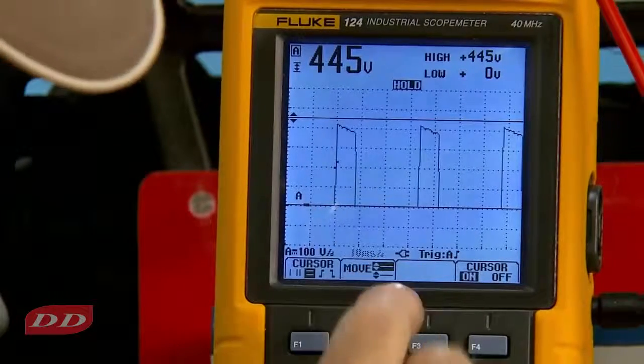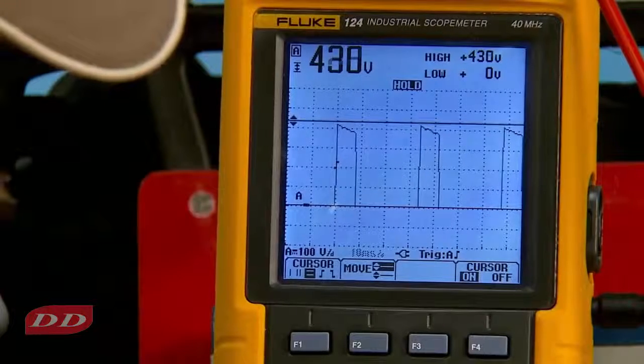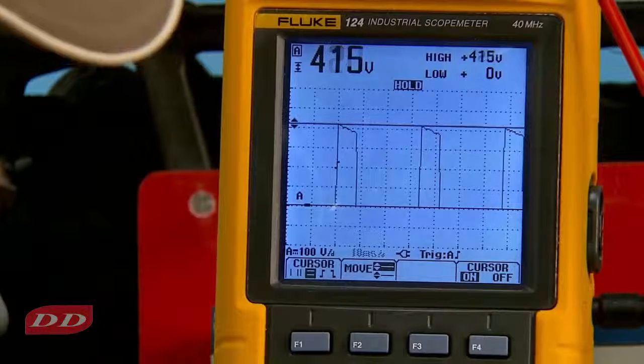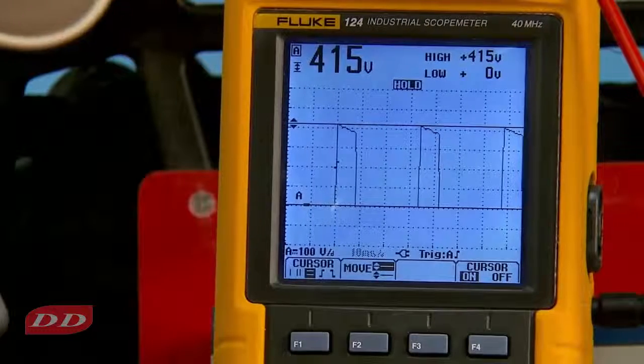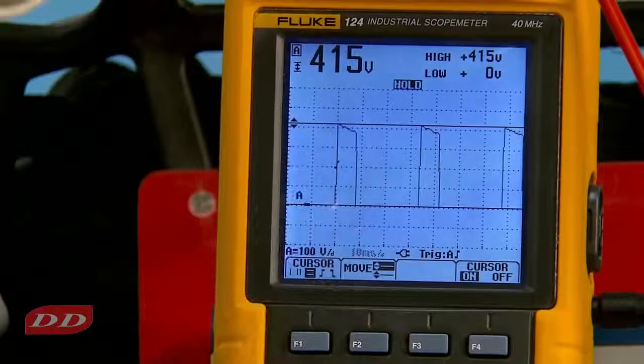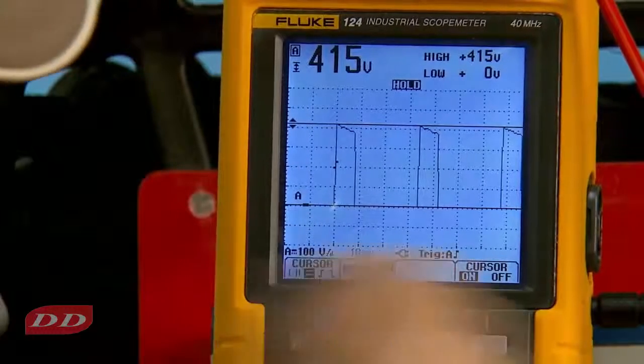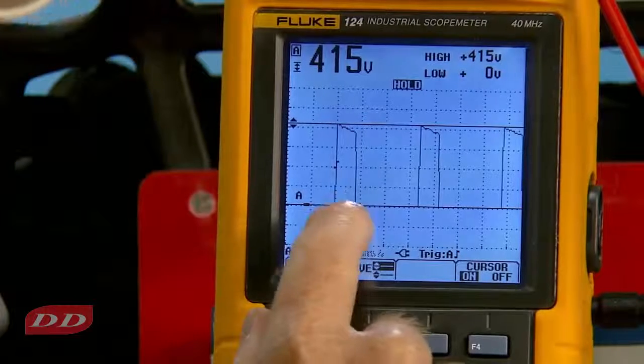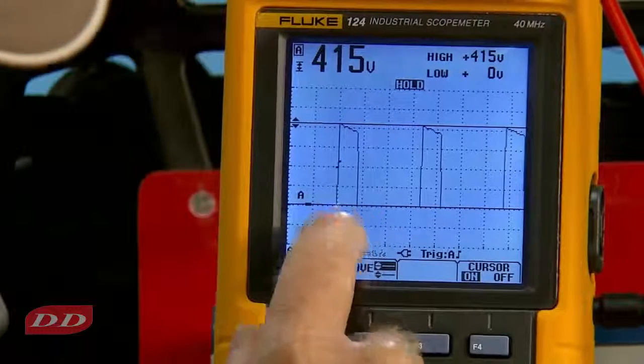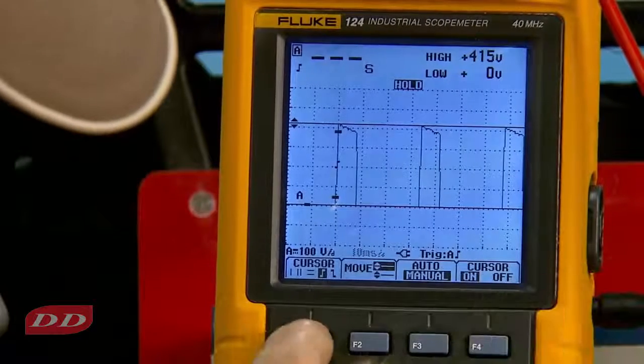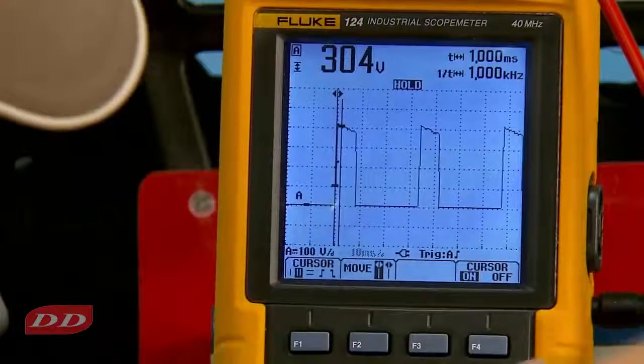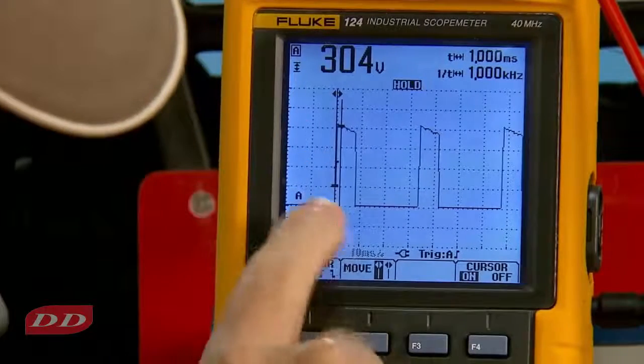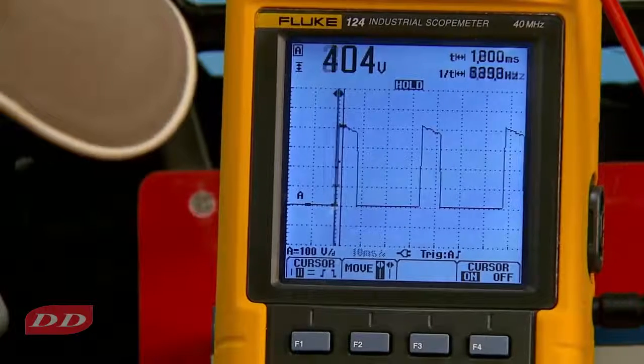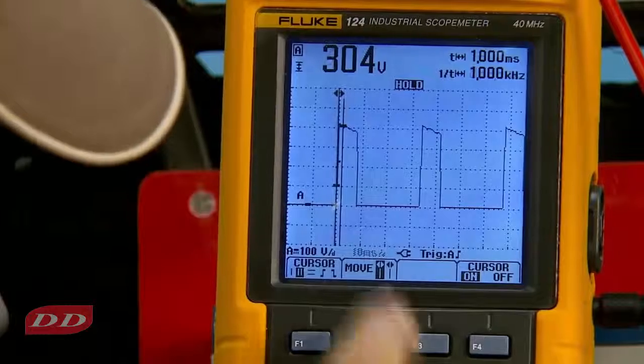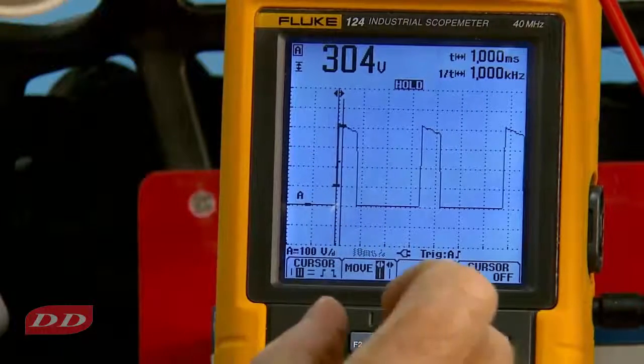And here are our vertical cursors. If we go to the very tip of the waveform, maybe right there or possibly there, we see the reading of 415 volts. This corresponded fairly close to the multimeter reading. Now, if we look at the width of the pulse, it's basically 4 milliseconds across, but if we use our horizontal cursors, from here to there is the point that the pulse width is 1 millisecond wide.